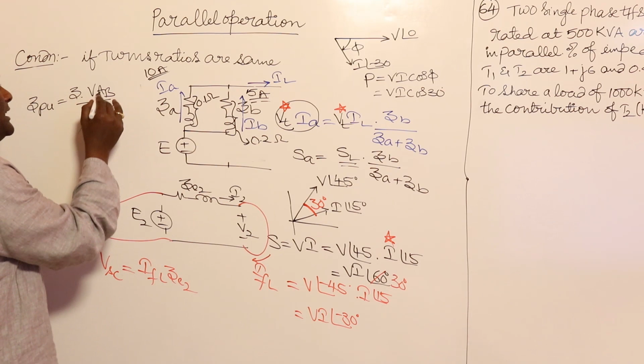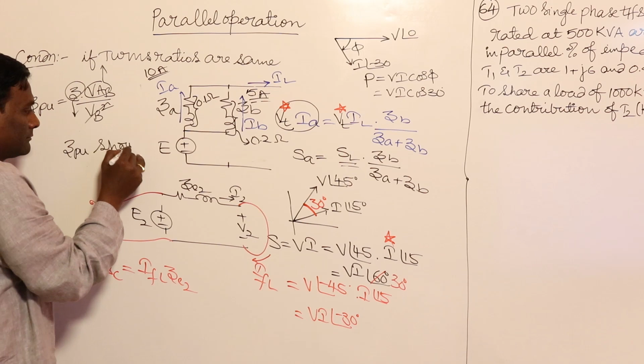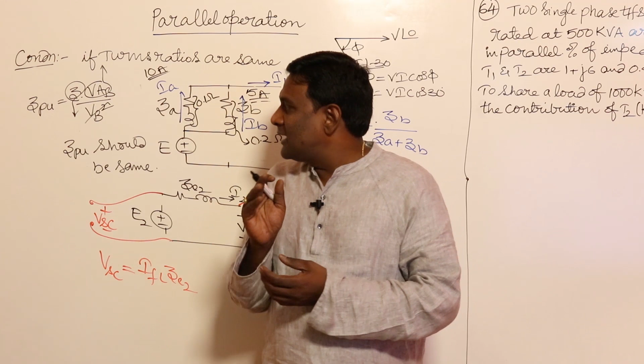Means that for a high capacity machine, impedance should be less. For a less capacity machine, impedance should be more. For a low capacity machine, impedance should be more, such that Z per unit should be the same. So my 10 kVA machine should have less impedance, the 5 kVA machine should have more impedance, such that Z per unit, if you calculate with respect to 10 kVA for this transformer, and Z per unit with respect to its own kVA for the other transformer, both are the same. What does it mean? If you go back and see per unit quantities of transformers, we clearly discussed that. Let me write here.